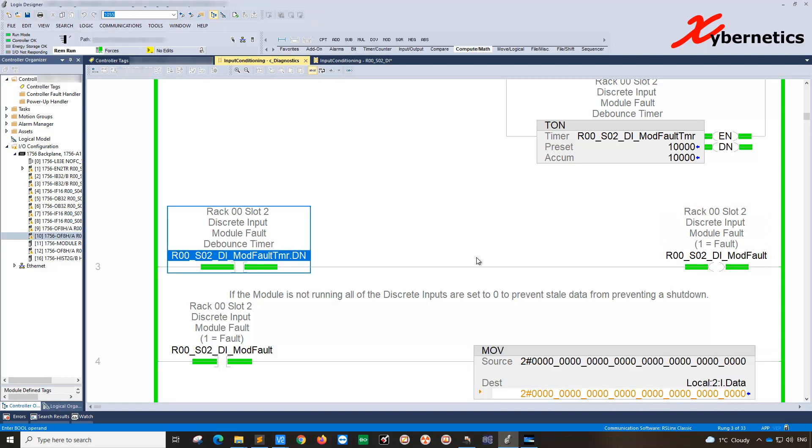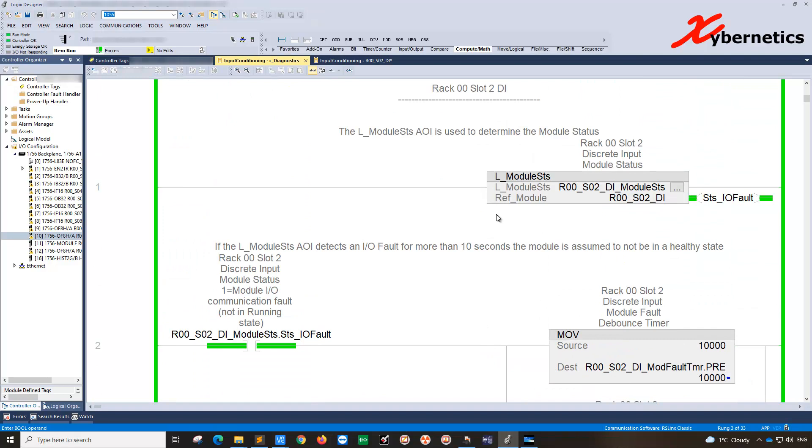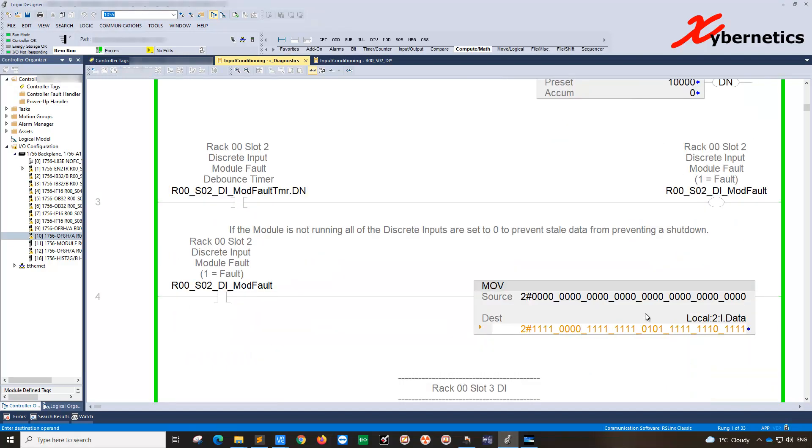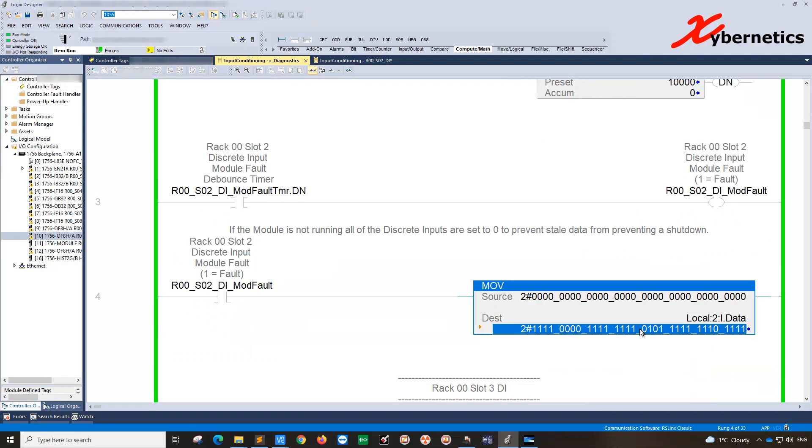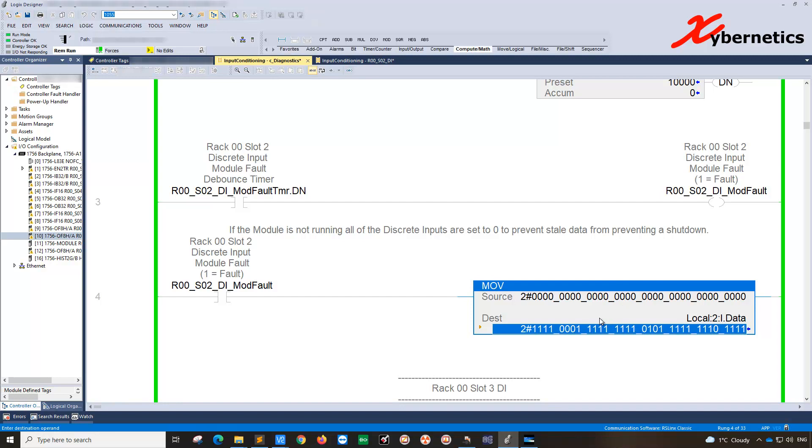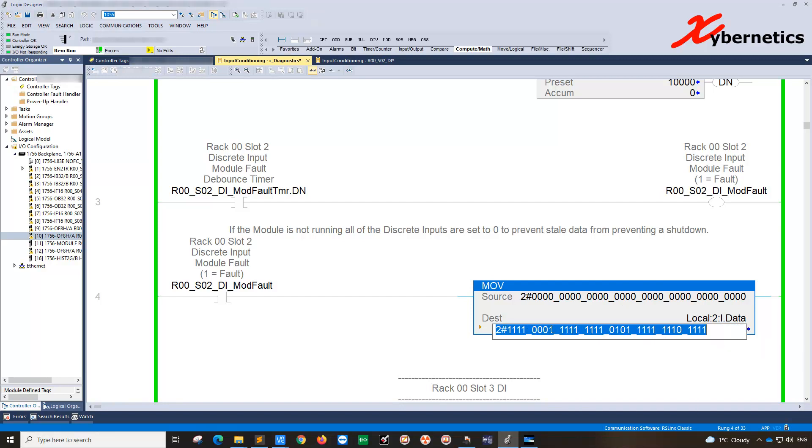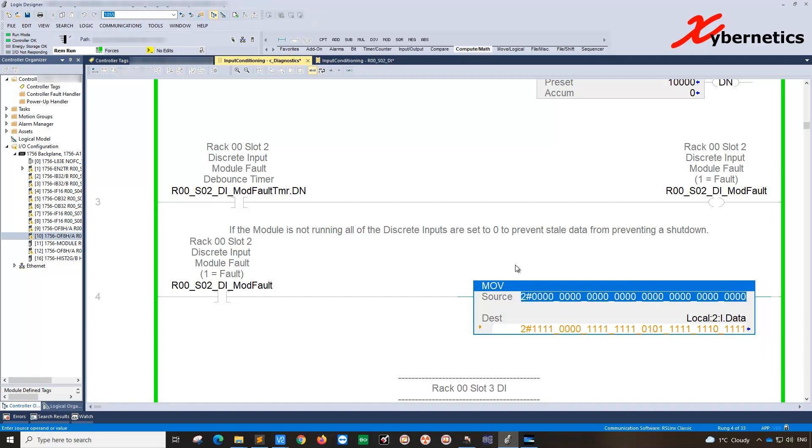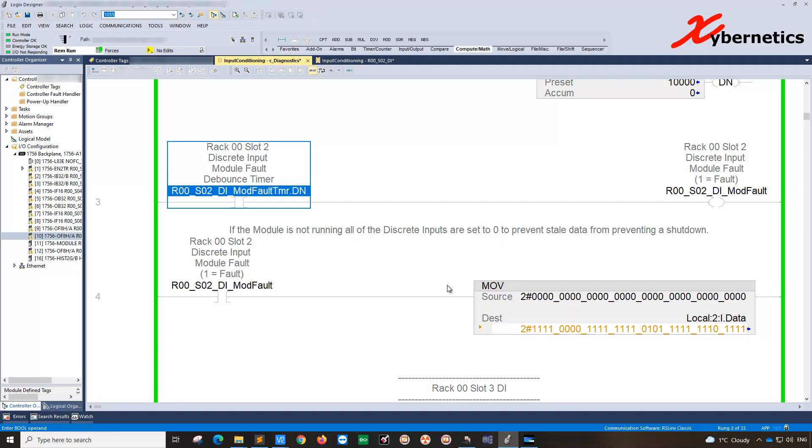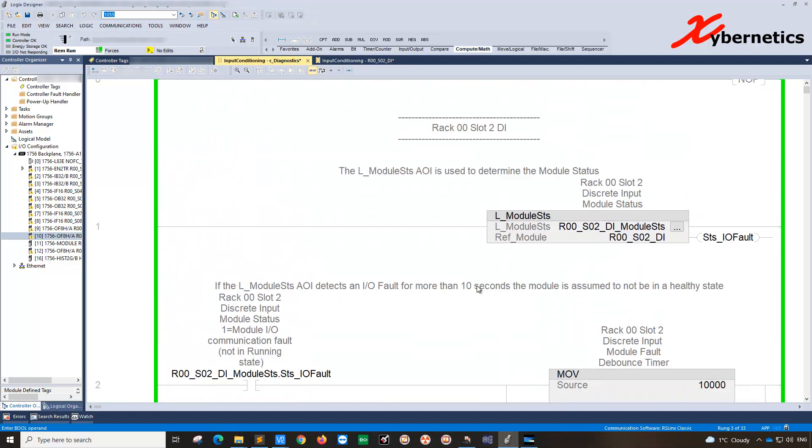I'm going to put this to simulate because this is my test bench, hit apply, and my fault clears. At this time you can go ahead and make changes to each of the bits and force values to the bit and all the test settings that you want to set. That's how you mitigate a module fault on a test bench.